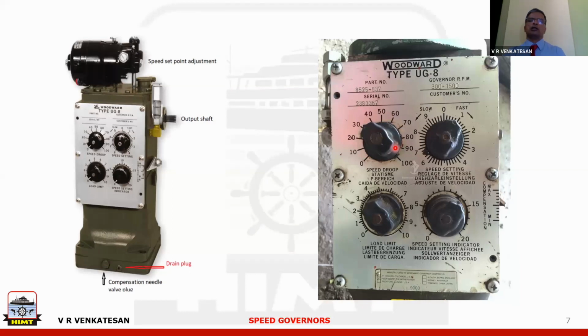So right now it is 30% of 4% that is the amount of droop that is set. So typically it will be between 30 to 50, the usual setting you will see in the droop. What do these mean? We will see. This is a local speed adjustment. This many of you would have seen.